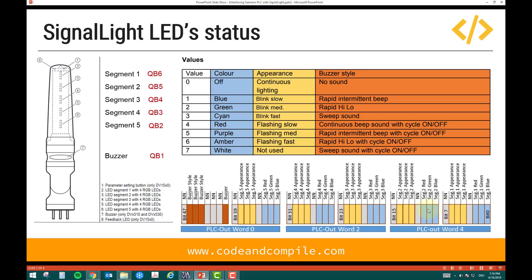Similarly, you have another byte for segment 2, another byte for segment 3, segment 4, and segment 5. Then you have the last byte for the buzzer. If you want to enable the buzzer, bit 0 should be true. Then bits 4, 5, and 6 define the buzzer sound — whether it's rapid, intermittent, high-low, sweep, or different sound signals.